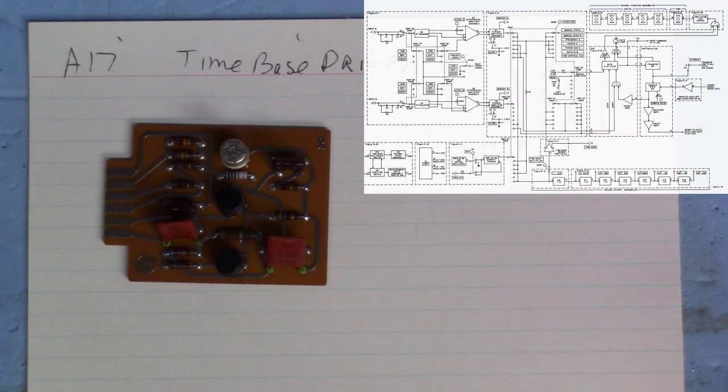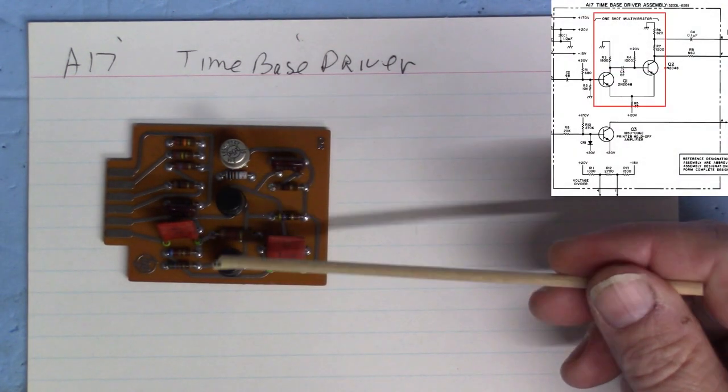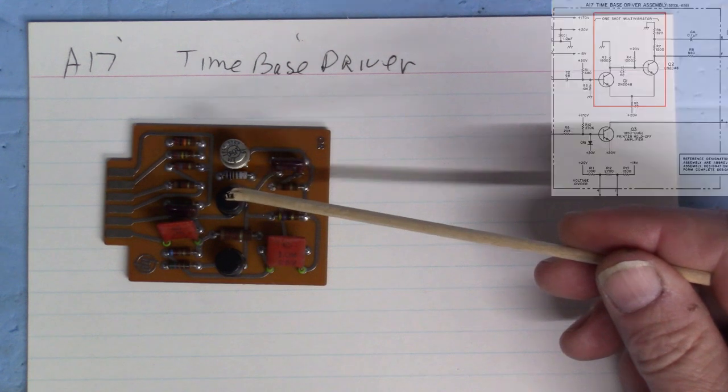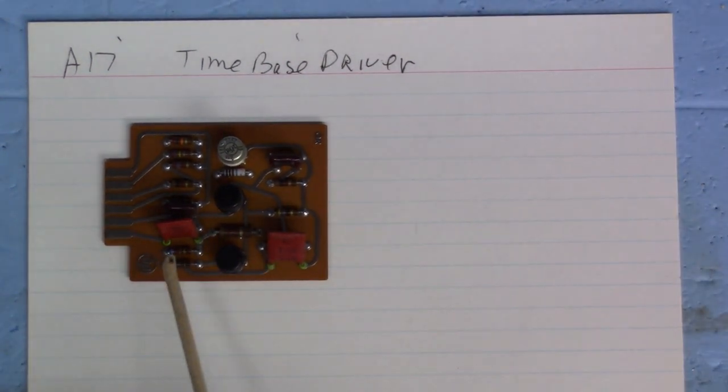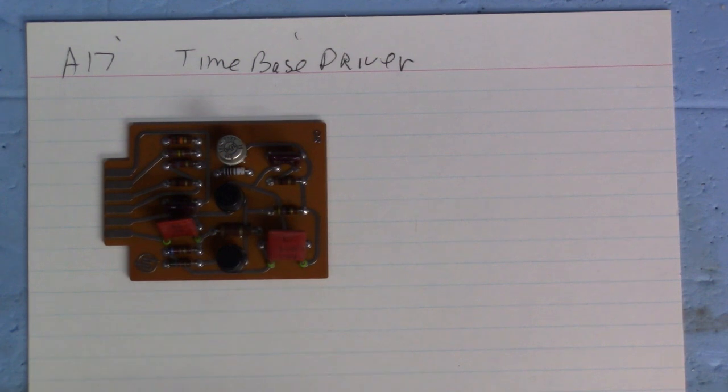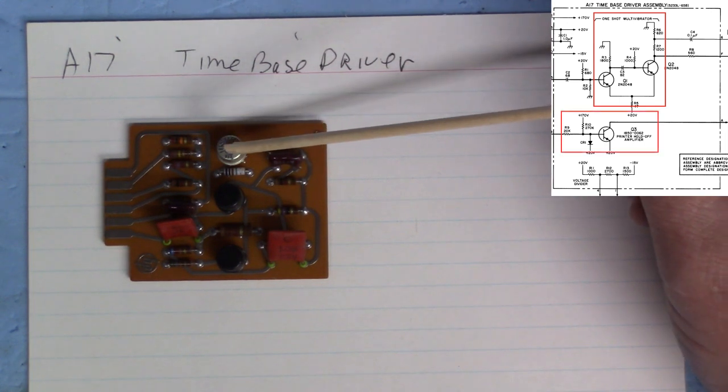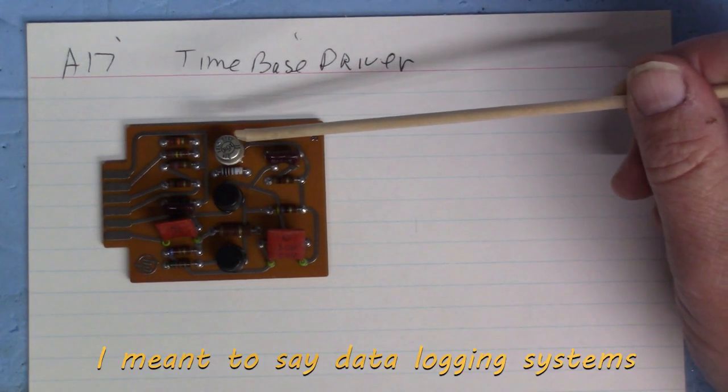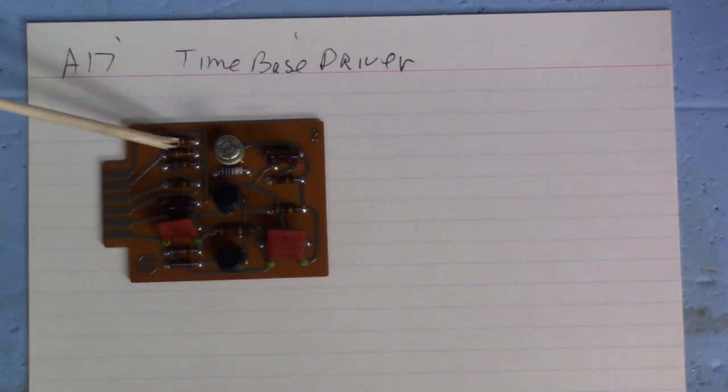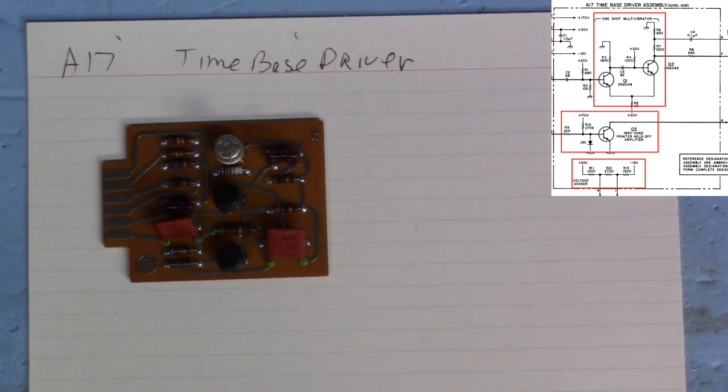Now back down to the time base driver. Again this is a really simple card, not much on this one but it's pretty varied. We have the one-shot multivibrator here that controls the time base. Again you see those ferrite beads and really tight tolerances. Again we have that one microfarad funny looking cap which is really an odd one to see in these things, but they all look okay. And the other thing we have on this is the printer hold off amplifier over here, and that holds the system off until the printer is finished printing. This is about the time that HP started integrating all sorts of printer functions and data logging systems. And the last little bit is this little bunch of resistors here which is a voltage divider that goes somewhere off on another board. The board's in fine shape, I don't think there's going to be any problem with this one.